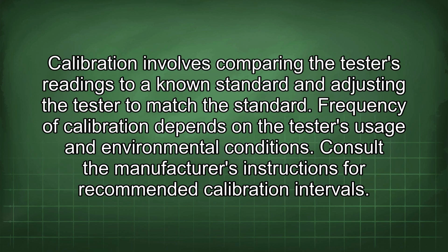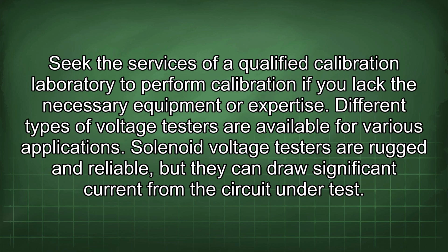Calibration involves comparing the tester's readings to a known standard and adjusting the tester to match the standard. Frequency of calibration depends on the tester's usage and environmental conditions. Consult the manufacturer's instructions for recommended calibration intervals. Seek the services of a qualified calibration laboratory to perform calibration if you lack the necessary equipment or expertise.